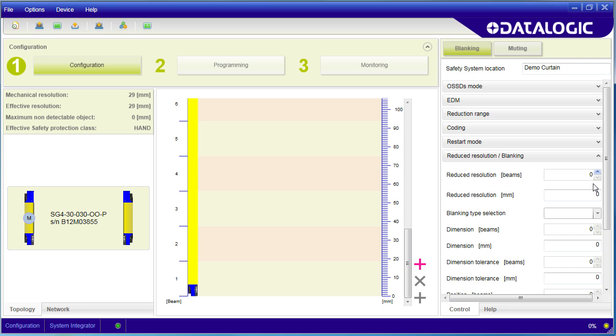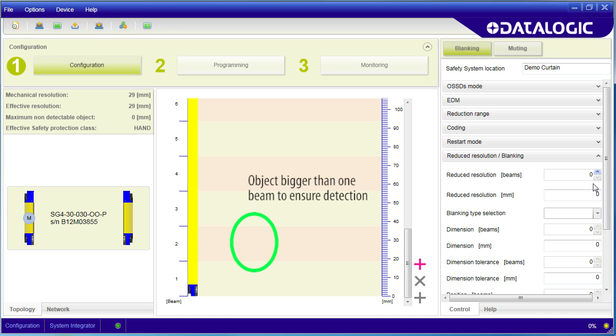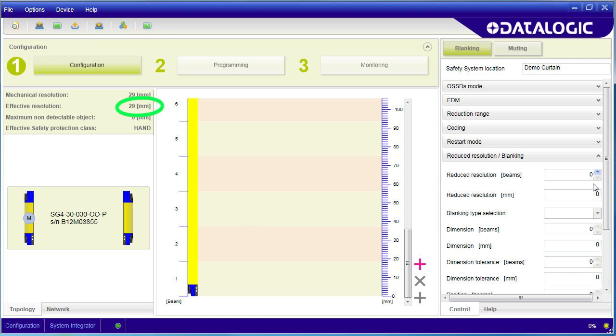So to ensure that at least one beam is always blocked you are going to need an object that is about 50% bigger than the width of one beam, hence this 29mm number. Given that, we have full coverage and this qualifies for hand safety class.